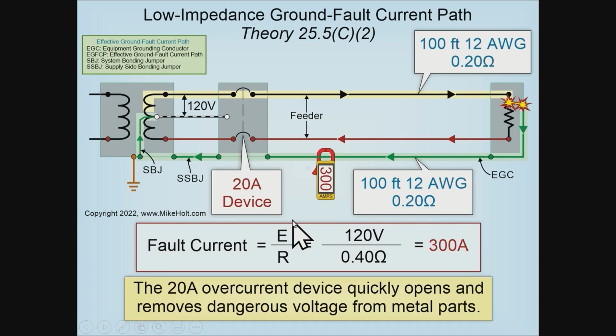Let me just kind of show a picture here. Okay, if there's a fault condition, when you have a ground fault, which is defined by the National Electrical Code, and we're having a phase wire touching metal parts that we've seen previously a couple of slides before, then the metal parts become energized. Now, the metal parts become energized until they open under a ground fault condition. And Tom, we don't know what the ground fault value is going to be under any set of circumstances. The wire could just be brushing against it. It could be bolted against it. When you have a ground fault condition, there could be some arcing that could take place. That creates impedance. The arcing also adds some impedance, meaning there's higher kind of resistance with AC. And depending upon the impedance of that ground fault determines the current of the fault.